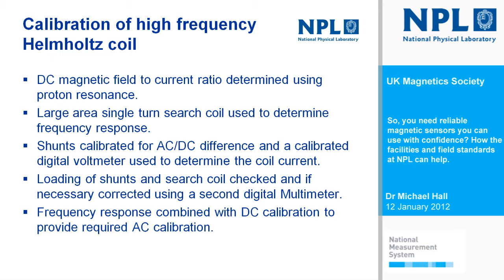And we use shunts which have known AC/DC difference, calibrated at NPL to measure the current that's flowing through the coil, and we therefore determine the coil constant against frequency through a combination of this DC value and the AC frequency response that we measure with the single coil. And this is the behaviour that we get.